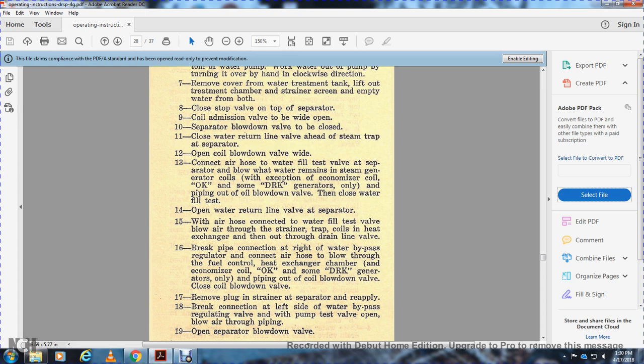the drain line valve. 16, break the pipe connection to the water bypass regulator for connection to the air hose. Blow through the fuel control and the heat exchanger chamber with the economizer coil, and the some DRK generators only, and piping out with the coil blow down valve. Close the coil blow down valve. 17, remove the plug with the strainer and separator and reapply.